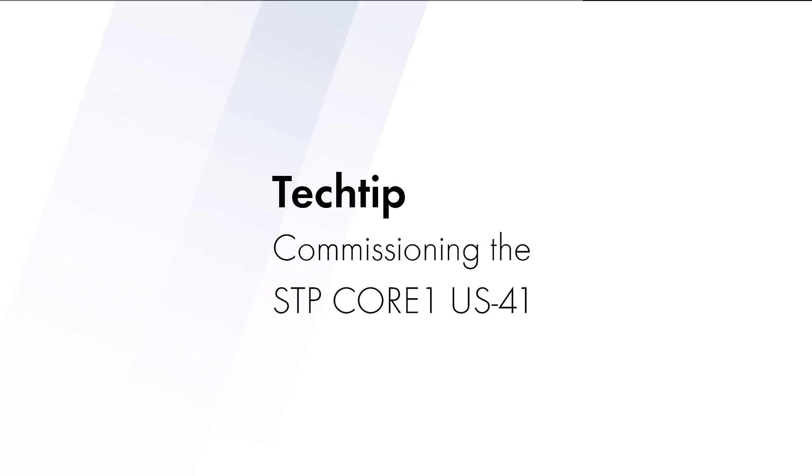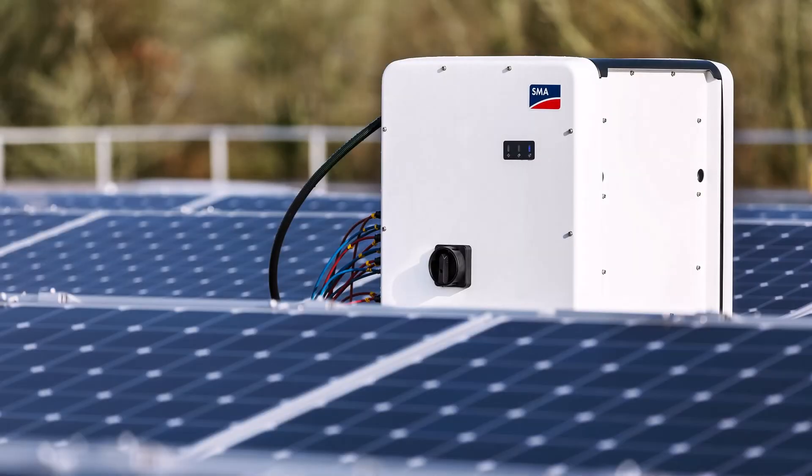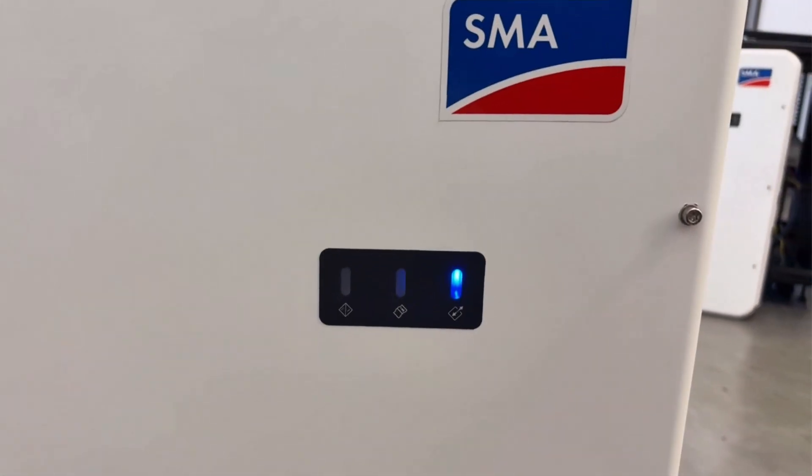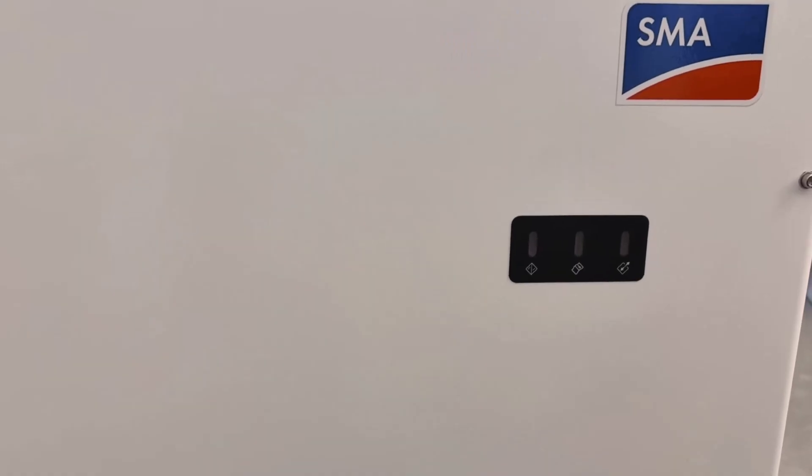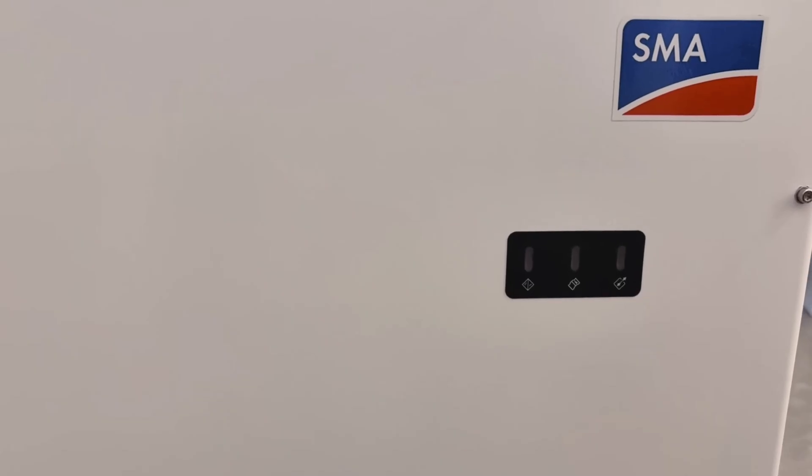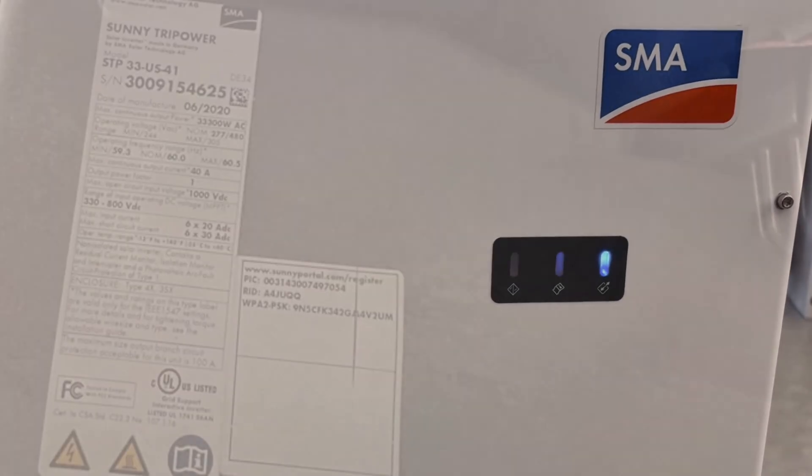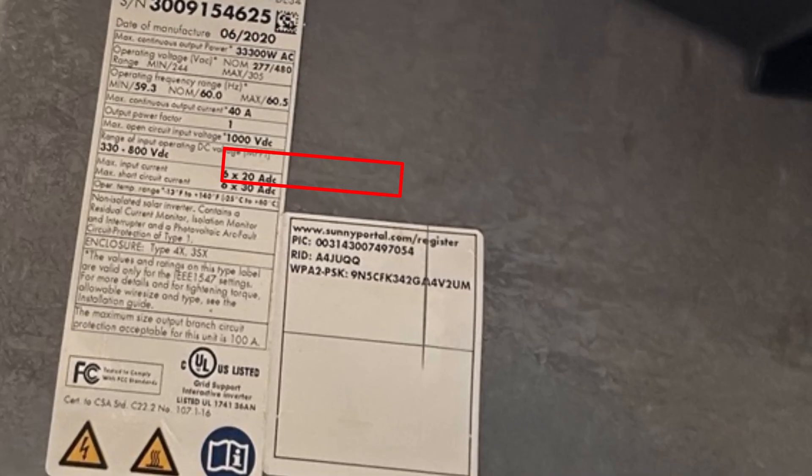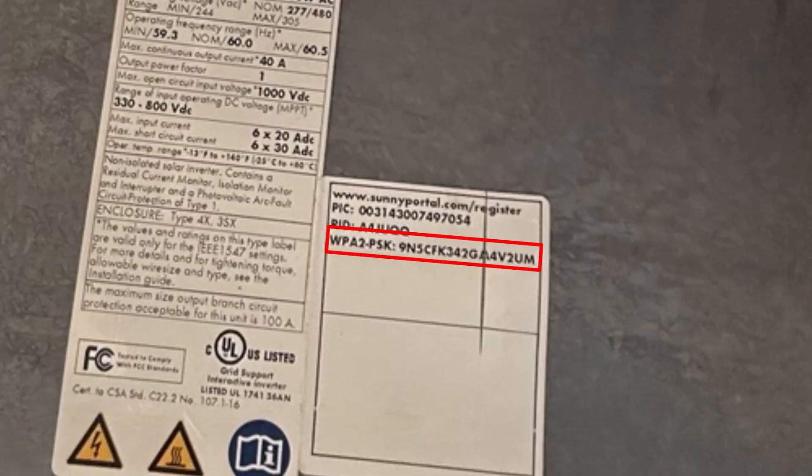Let's commission the SMA Sunny Tripower Core 1. After installing the Core 1, knock on the inverter lid to wake it up. Wait until the blue LED starts blinking. On your device, go to the WiFi settings and look for a network that is SMA followed by the device serial number.